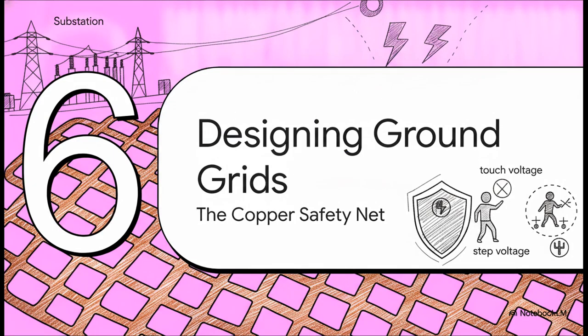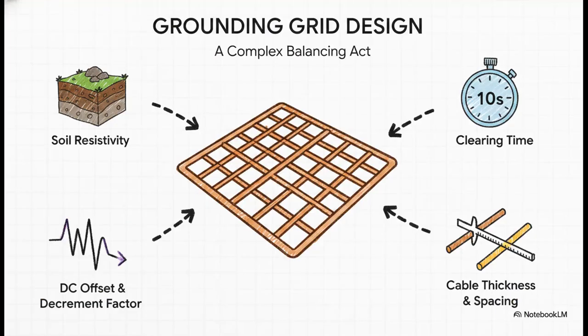Section 6. Designing the ground grid. So how do we guarantee those step and touch voltages stay below the lethal threshold? We build a massive, invisible copper mesh buried beneath the substation, and designing this grounding grid is an incredibly complex balancing act. Engineers have to combine geological factors, like the specific resistivity of wet crushed rock, with highly complex electrical factors. They must factor in the clearing time of backup relays, just in case the primary ones fail. They calculate the system's X/R ratio, which dictates the decay of the DC offset, and they apply a decrement factor to account for asymmetrical fault currents.